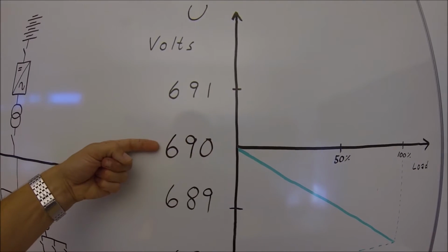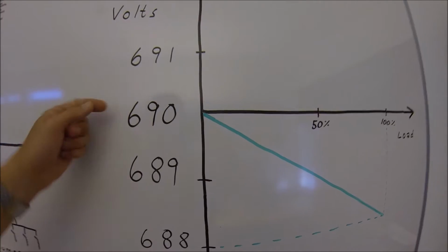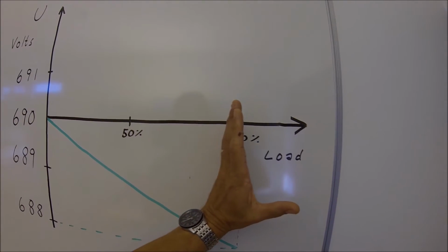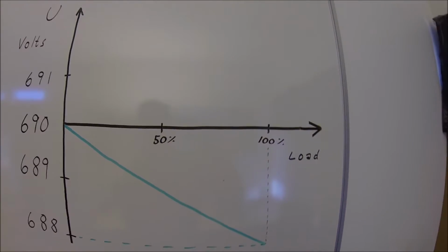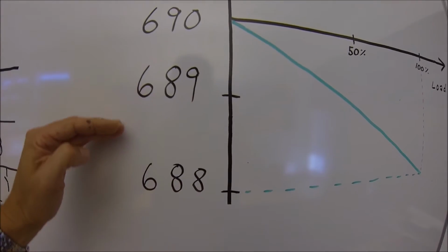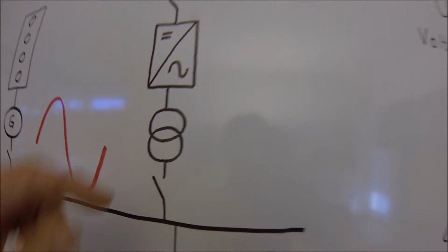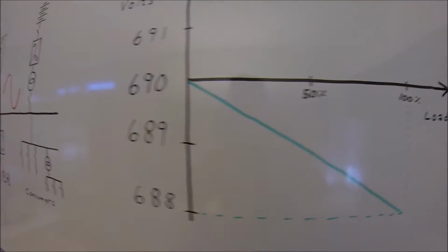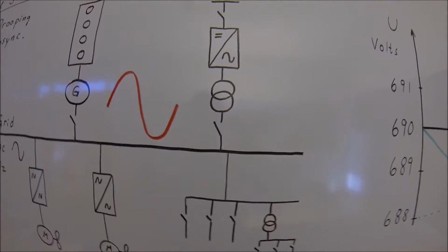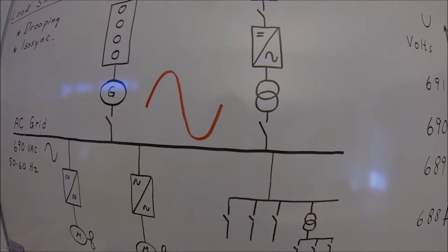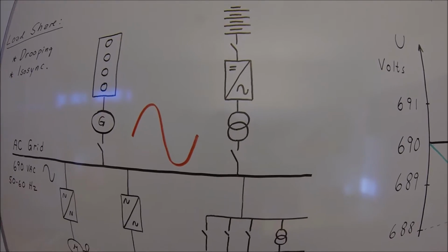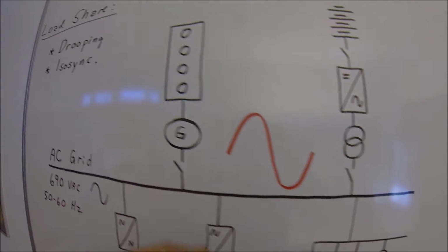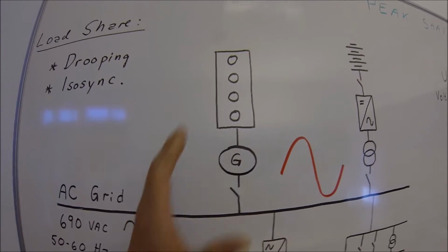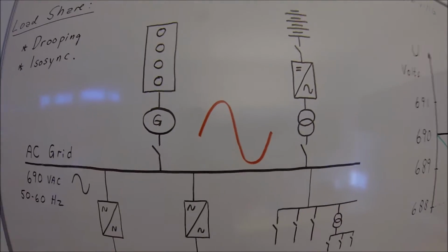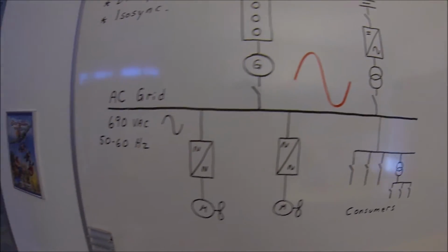If we aim for 690 volts, it means that when the reactive current is going up to 100% of the drive nominal current rating, we reduce the voltage produced from here. When we reduce the voltage, the load will back off a little bit. So in this way, we back off our share of the reactive load on the grid. If we have the same drooping on the voltage on the energy storage as the diesel generator, they will take about the same proportional part of the reactive load on the grid.